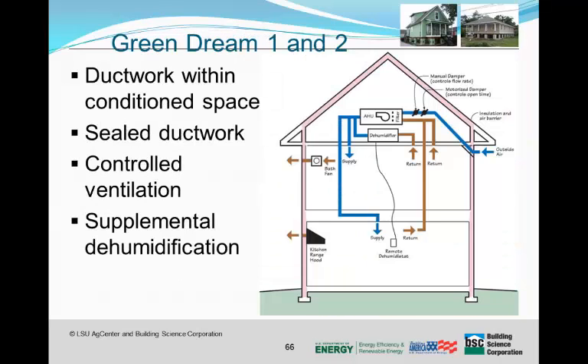A big factor in achieving really high performance from an energy standpoint is to eliminate duct losses in that air conditioning system by putting all of the system, including the ductwork, within the conditioned space - inside the thermal envelope, the boundary of where insulation and air barrier is. Of course, the ductwork is also sealed tight, so it will get to where you want it to be.